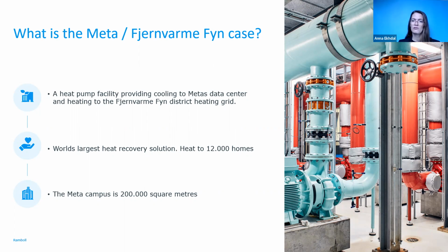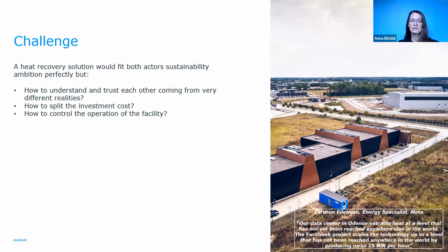Today, there has been 45 megawatts installed, and there are another 40 additional megawatts in plan. And this makes the largest heat recovery from a hyperscaler in the world. So on the next slide, I will be talking a little bit more about the challenges that the actors were facing. When it was clear that Meta was about to build a data center in Odense, they were coming from a perspective that they had a sustainability ambition and wanted to know what the business case for heat recovery could look like.